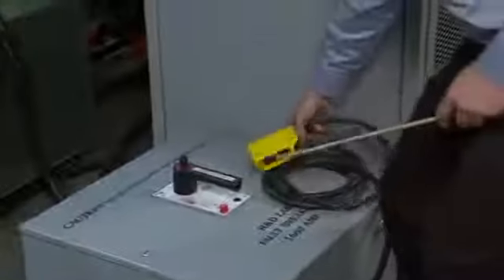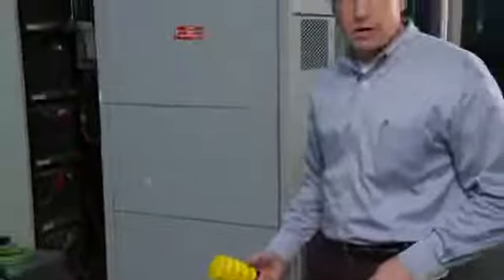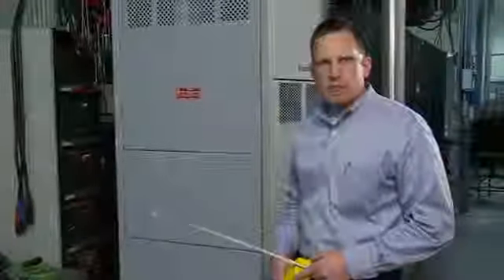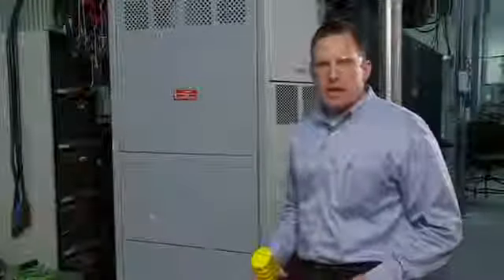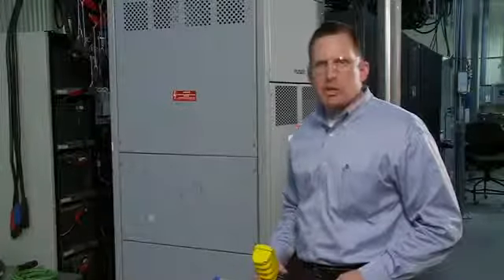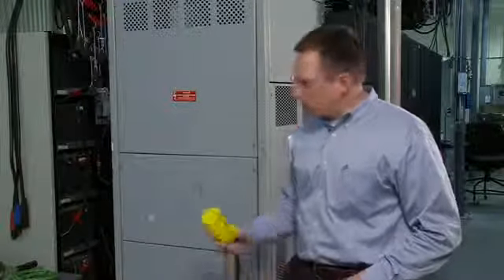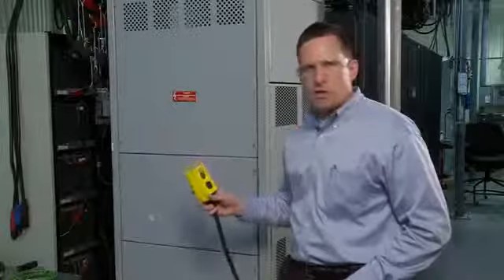Now to the side of the unit, we have the 1600 amp faulting breaker that we're going to use to apply the short circuit mentioned previously. Again, that is to the battery plus connection to the chassis ground connection. We will use this control to apply that short circuit.